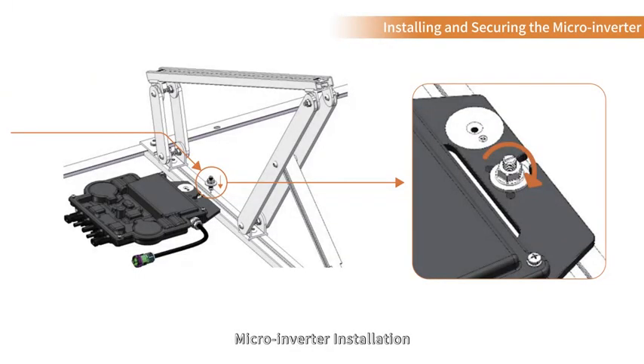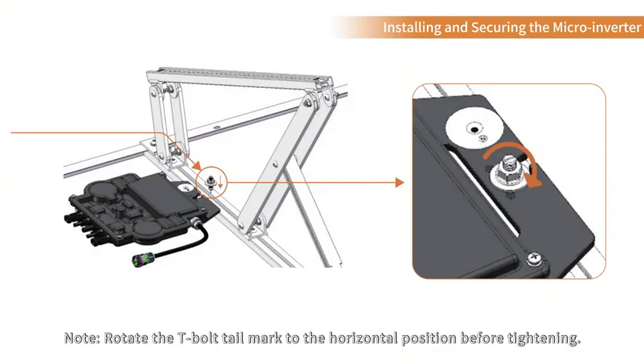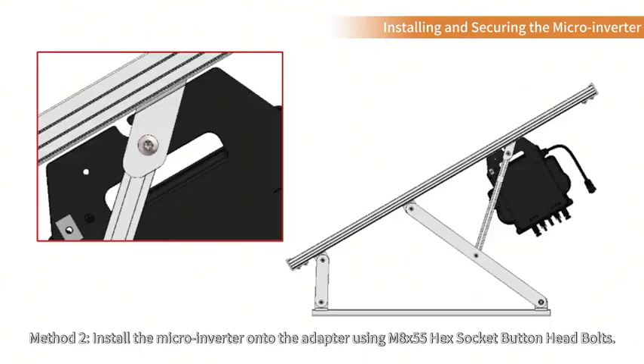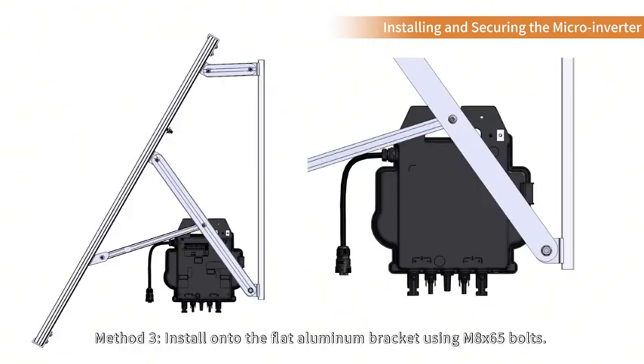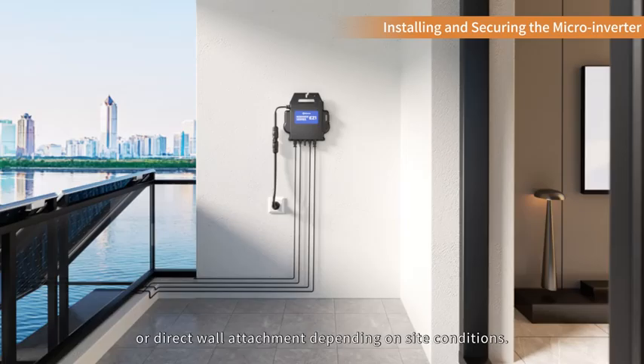Microinverter installation. Method 1. Secure the microinverter using M8X25T bolts. Note, rotate the T-bolt tail mark to the horizontal position before tightening. Method 2. Install the microinverter onto the adapter using M8X55 hex socket button head bolts. Method 3. Install onto the flat aluminum bracket using M8X65 bolts. This is better suited for wall mounting or direct wall attachment depending on site conditions.